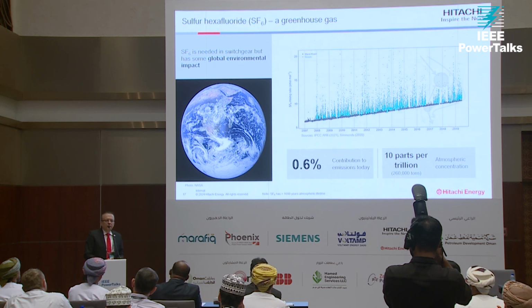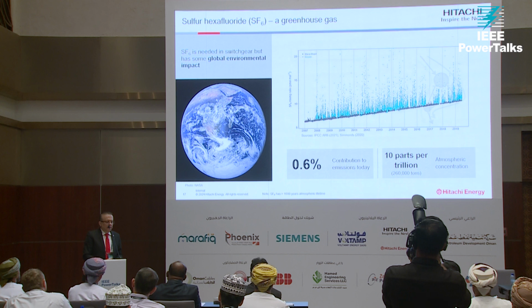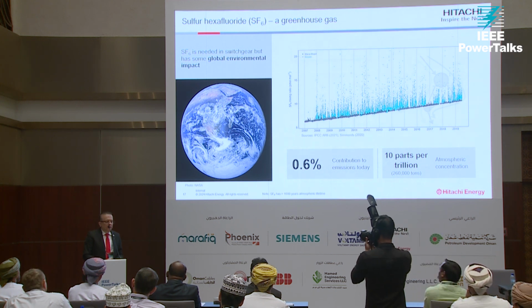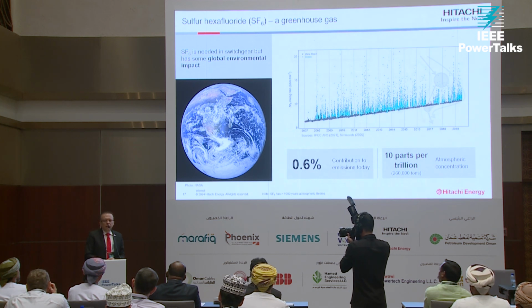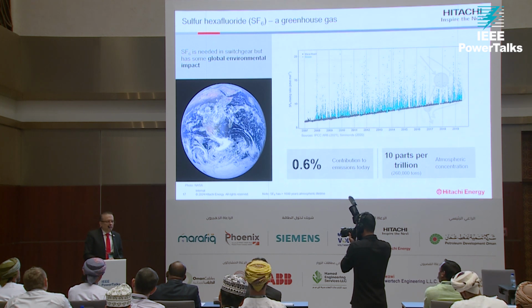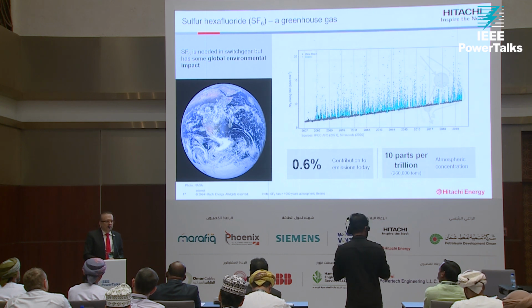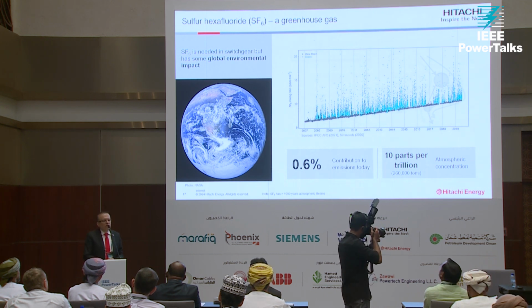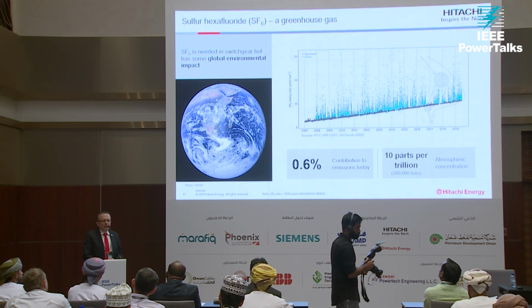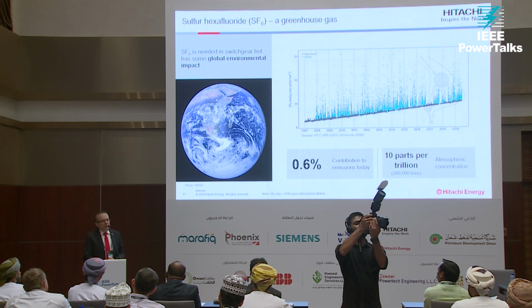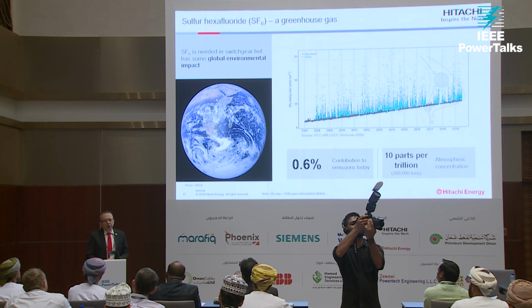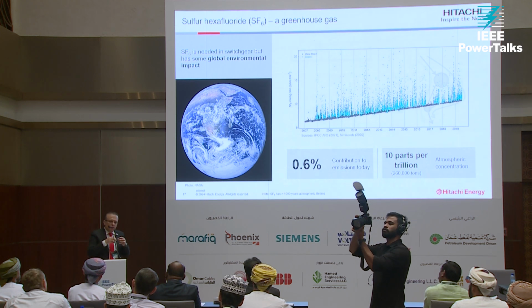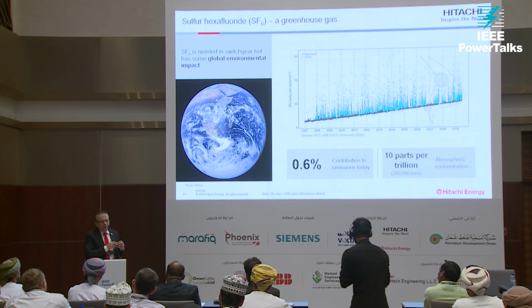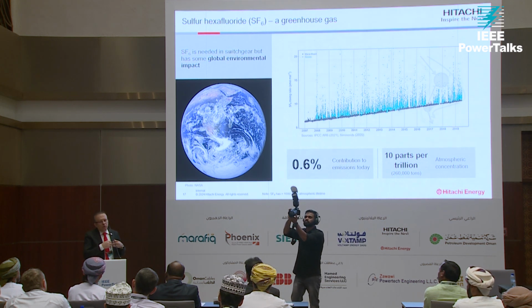To make permeation simpler: when you receive a GIS or switchgear from any OEM - Hitachi Energy or others - you do the FAT at the factory, check the gas pressure and check for leakage, and everything is fine. But after 5 years, you'll see the pressure has reduced a little. Why? This is due to permeation - the SF6 molecules, after a while, move inside the molecules of the sealing and other parts, and day by day, month by month, they migrate through.